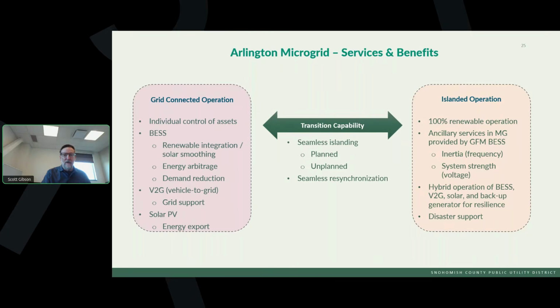When it was islanded, the grid forming inverter would take over as the balancing authority, maintaining voltage and frequency. When grid connected, it just follows the grid - BPA, the Bonneville Power Administration, is our balancing authority, and they maintain voltage and frequency while we follow it. When islanded, the grid forming inverter has to take over and do all that. That's the beauty of a grid forming inverter - it had this power conversion system, and the battery inverter had software called virtual generator mode that allowed us to do that. Pretty cool stuff.